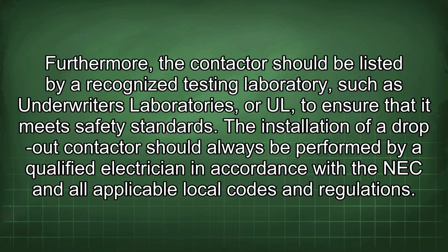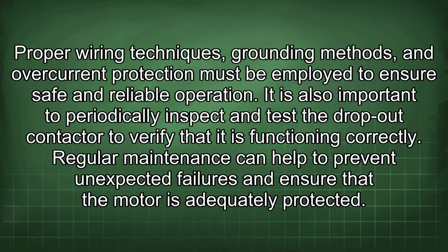The installation of a dropout contactor should always be performed by a qualified electrician in accordance with the NEC and all applicable local codes and regulations. Proper wiring techniques, grounding methods, and overcurrent protection must be employed to ensure safe and reliable operation. It is also important to periodically inspect and test the dropout contactor to verify that it is functioning correctly. Regular maintenance can help to prevent unexpected failures and ensure that the motor is adequately protected.